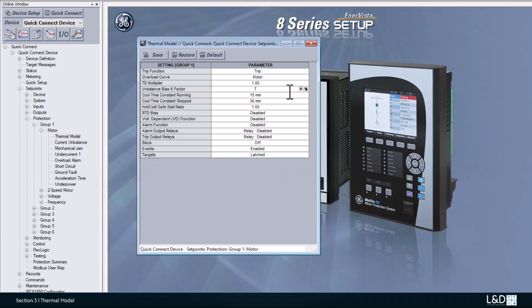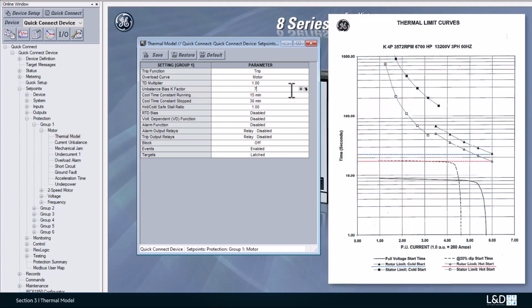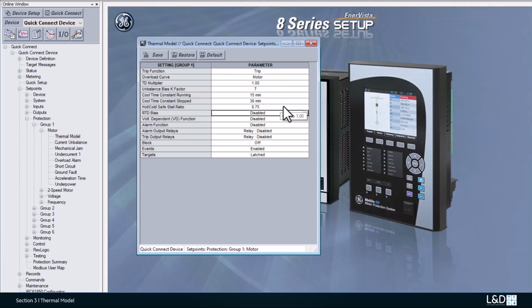For the hot and cold curve ratio, which is calculated by simply dividing the hot safe start time by the cold safe start time, this information can be extracted from the thermal model curve. From the motor thermal limits curve, we can determine that the hot safe start time is approximately 18 seconds and the cold safe start time is approximately 24 seconds. Therefore, the hot-cold curve ratio should be programmed as 0.75 in this example.